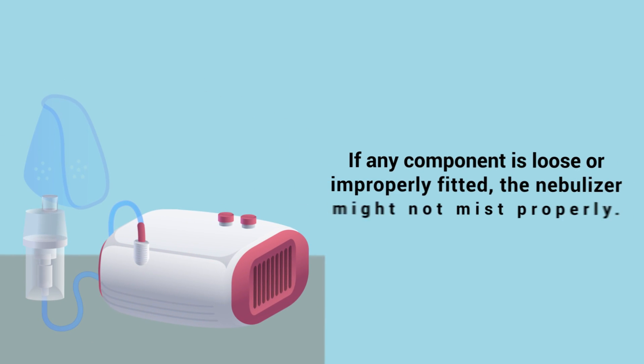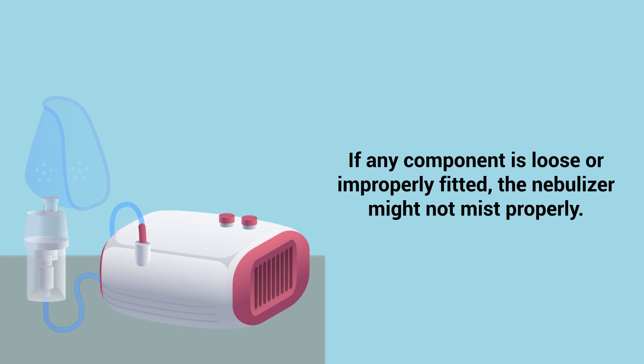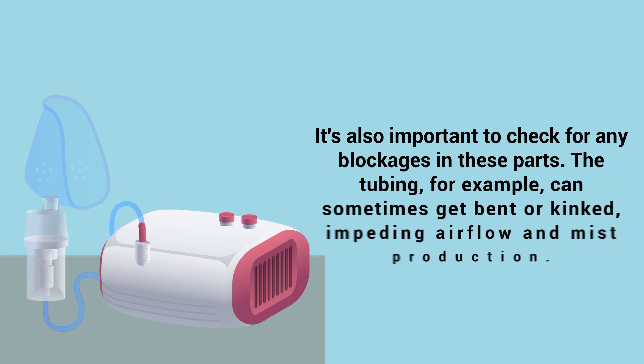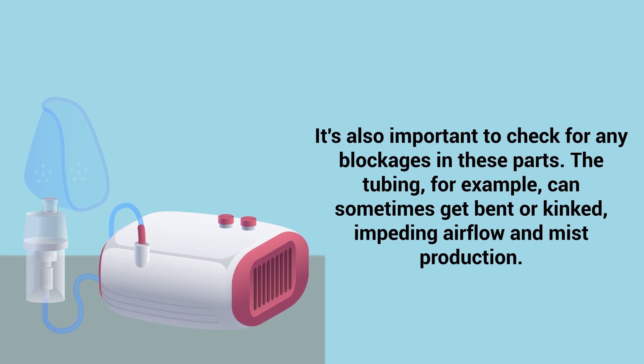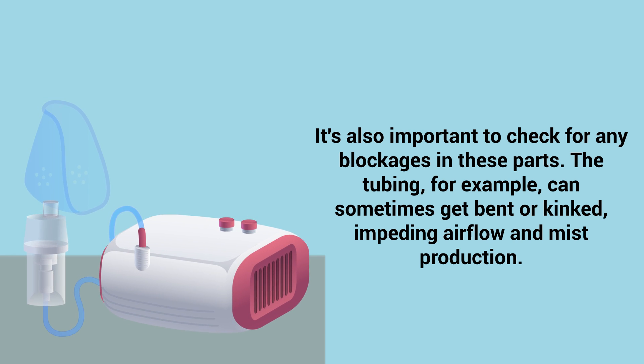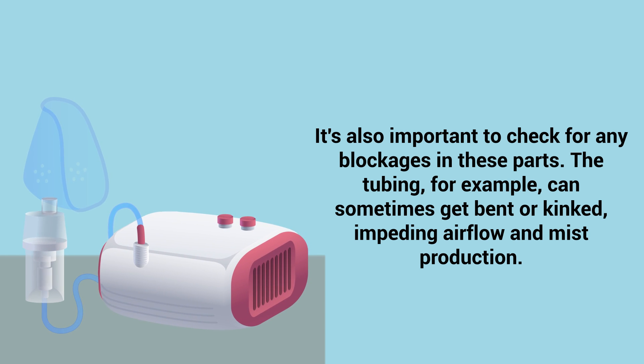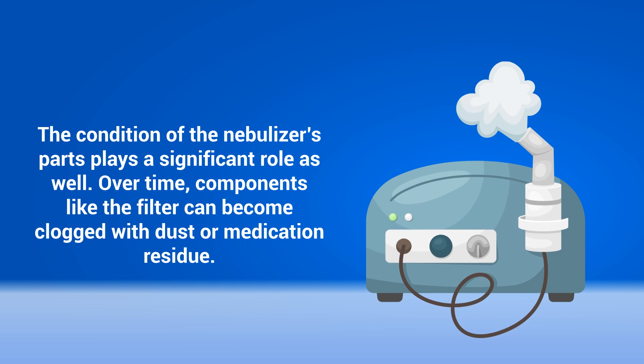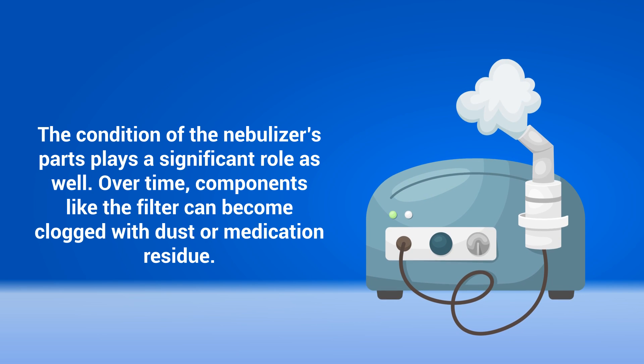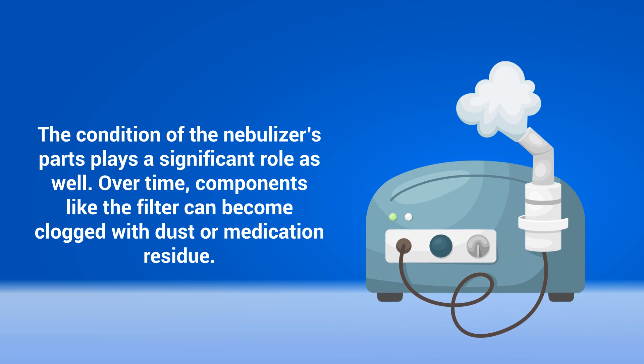If any component is loose or improperly fitted, the nebulizer might not mist properly. It's also important to check for any blockages in these parts. The tubing, for example, can sometimes get bent or kinked, impeding airflow and mist production.